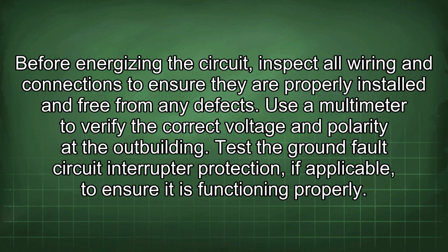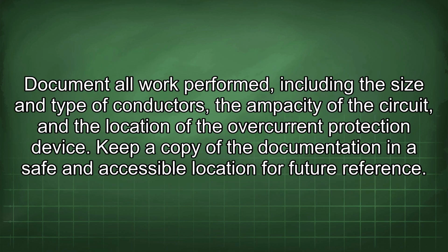Use a multimeter to verify the correct voltage and polarity at the outbuilding. Test the ground fault circuit interrupter protection, if applicable, to ensure it is functioning properly. Document all work performed, including the size and type of conductors, the ampacity of the circuit, and the location of the overcurrent protection device. Keep a copy of the documentation in a safe and accessible location for future reference.